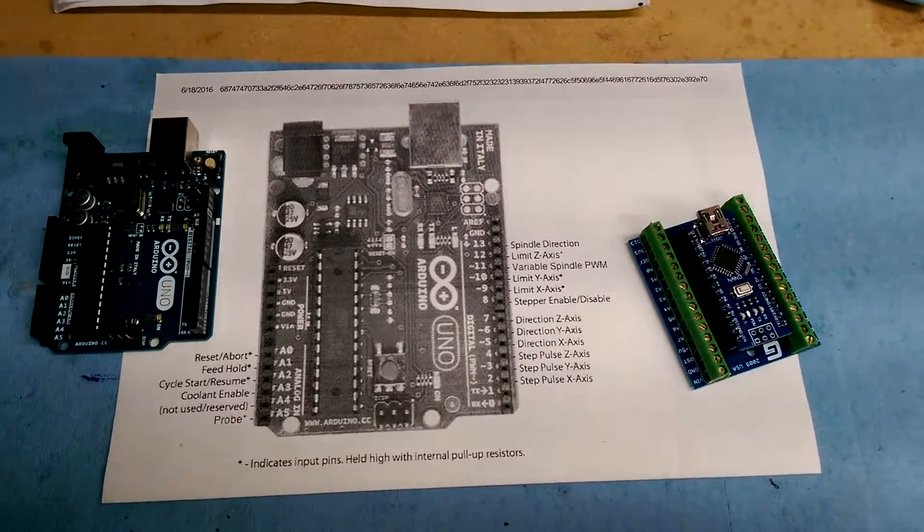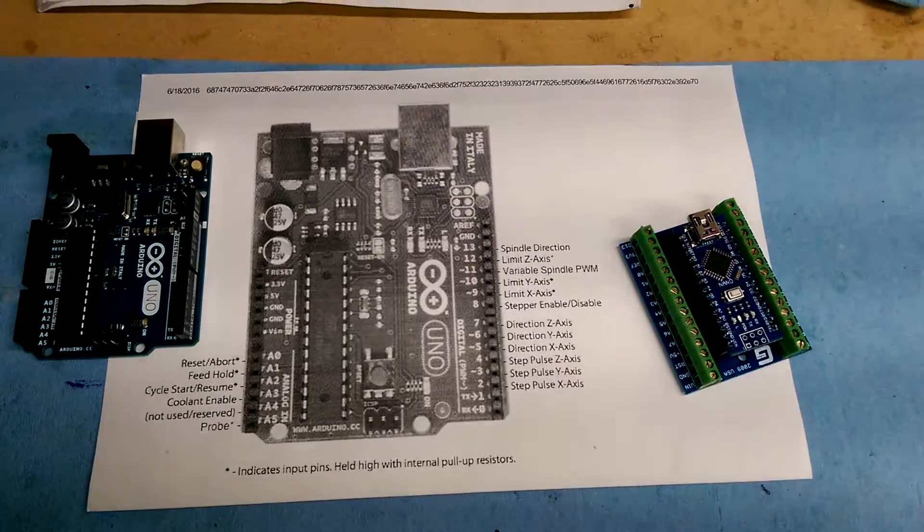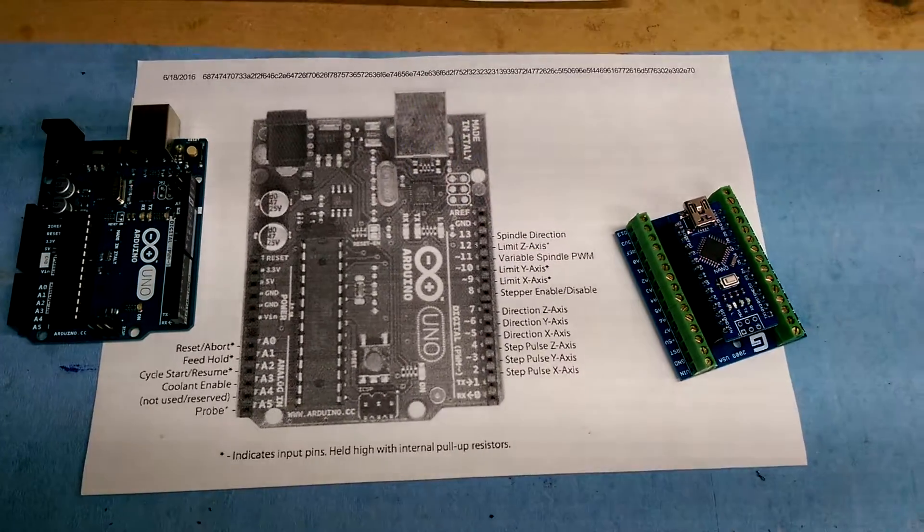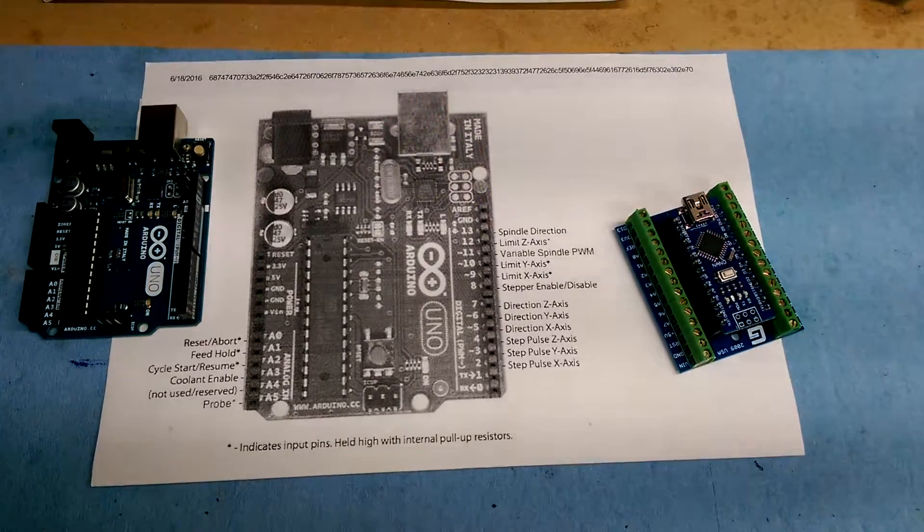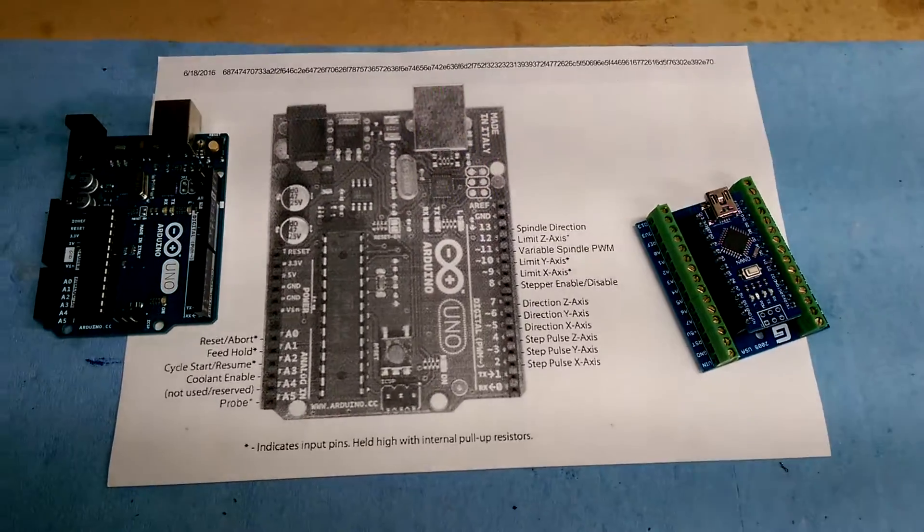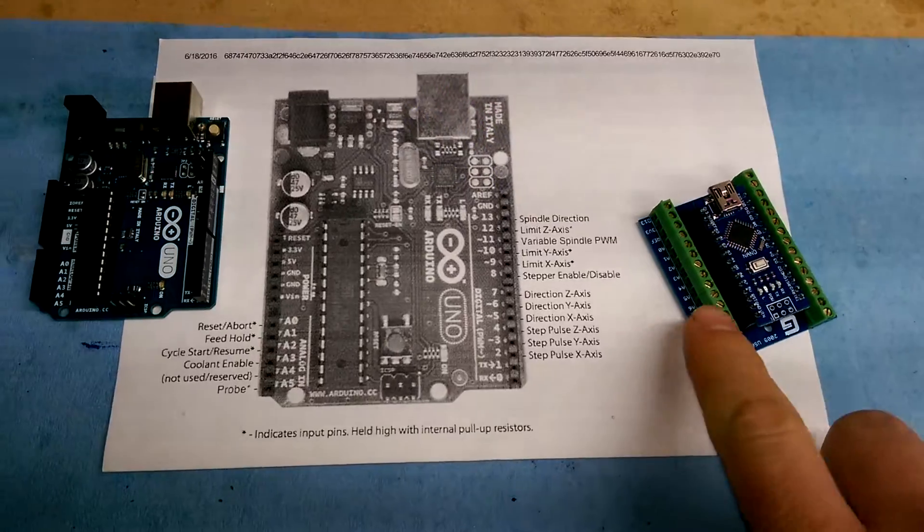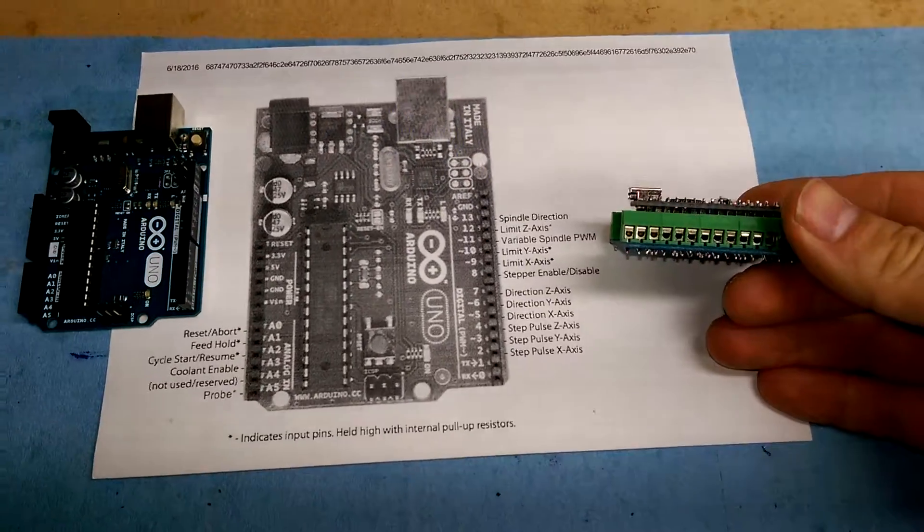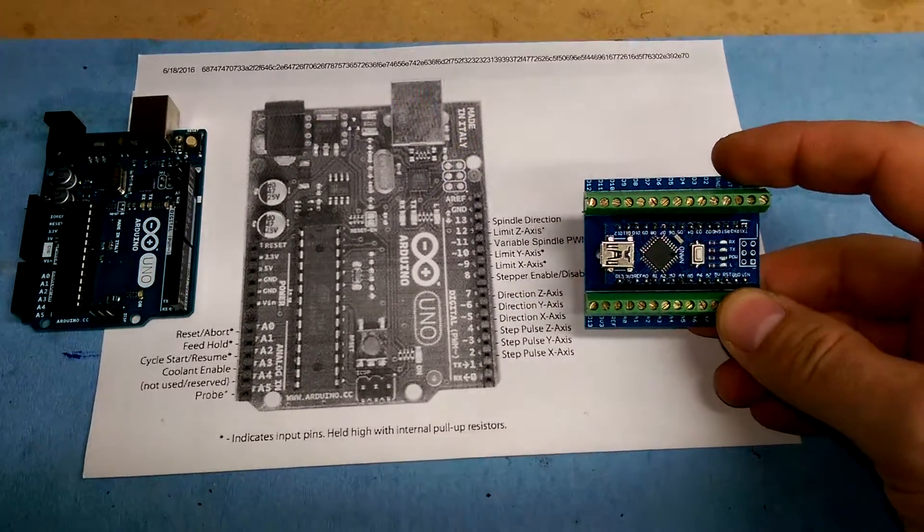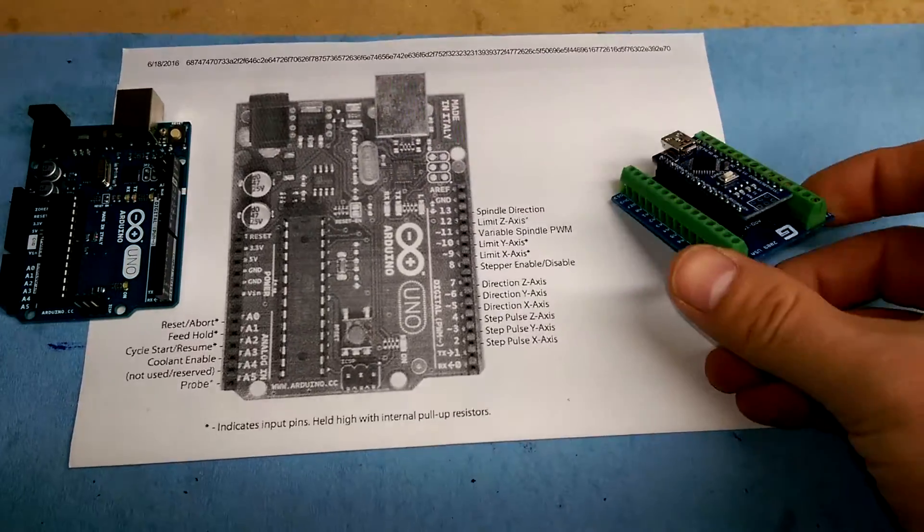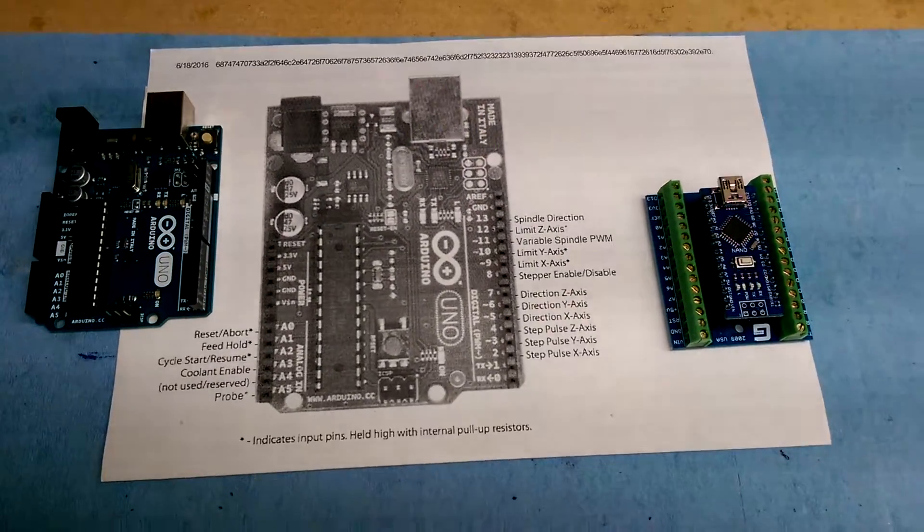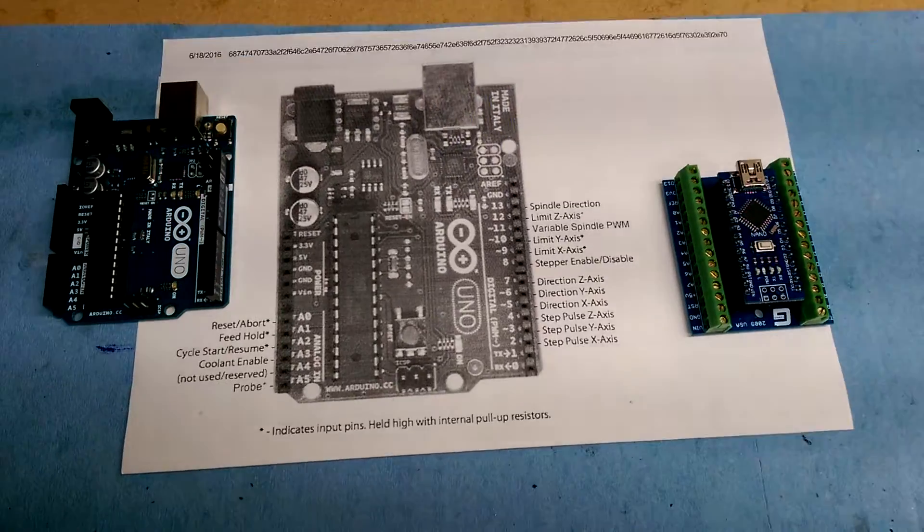The other problem, biggest problem I was having on this though, was that a lot of these require a grounding wire to come in to it as well. If you've got four or five, six ground wires coming in trying to go into one or two of these little terminals on these terminal blocks, it gets really difficult.